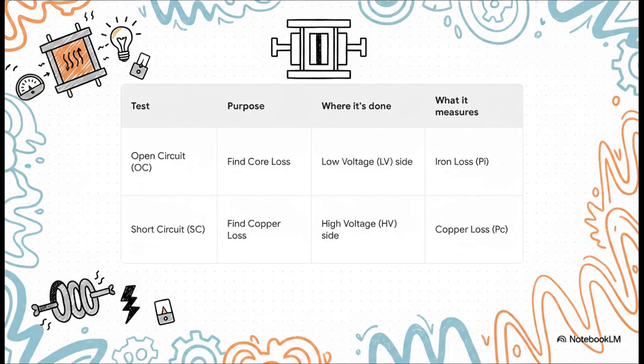So how do you actually separate and measure these two different kinds of loss? Engineers have two clever tests for this. First, an open circuit test on the low voltage side, perfect for isolating and measuring those constant iron losses. Then a short circuit test on the high voltage side to figure out the copper losses that happen when it's working hardest at full load. Run both of those and you've got a complete performance profile for that transformer.